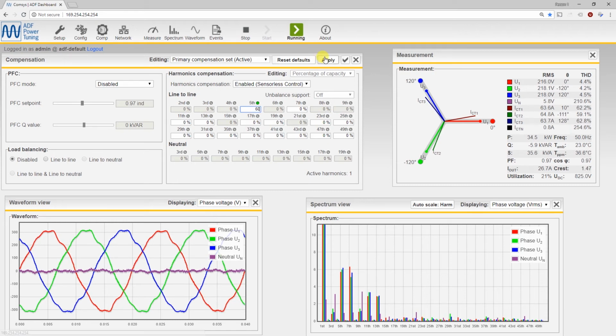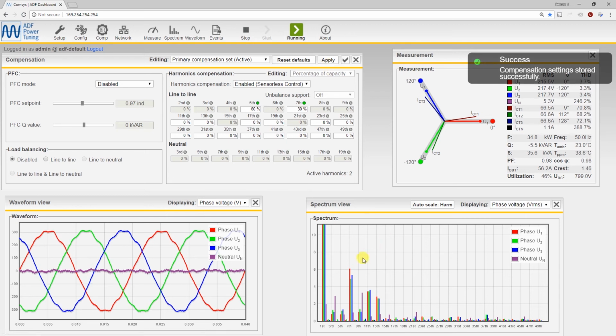Let's go to 60%, and with 60% we are pretty far down already. We have already an output current of 56 amps. So it's actually not using the full 60% that we're allowing the filter here, but this is all the filter can do at the moment. Now we can add a little bit to the 7th harmonic, 30%, and that one is kicked down as well.